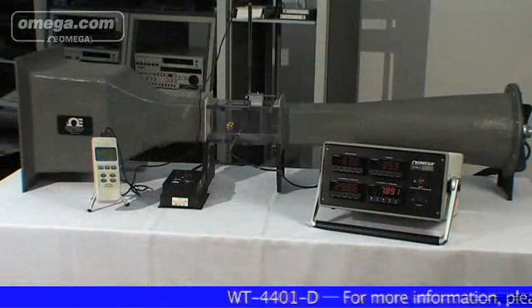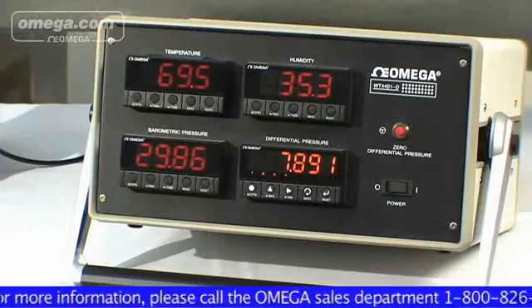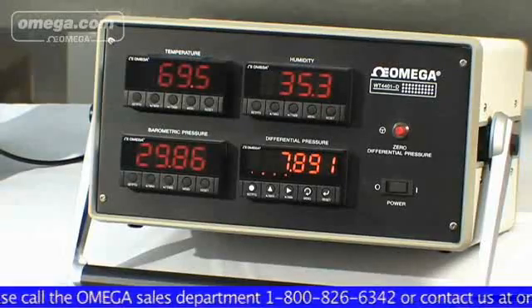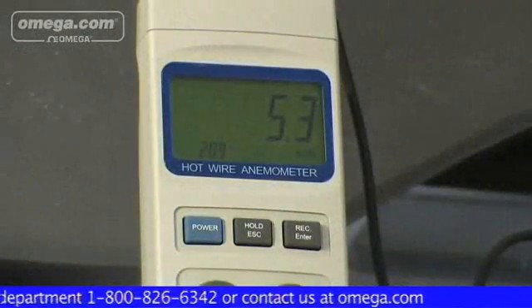Each wind tunnel is supplied with two restrictive plates for achieving optimum low flow rates. Omega also offers a deluxe wind tunnel package option as an environmental monitoring system that measures barometric pressure, room temperature, humidity, and differential pressure. By monitoring room conditions, standard differential pressures can be converted to actual differential pressure readings to ensure accurate flow rates.